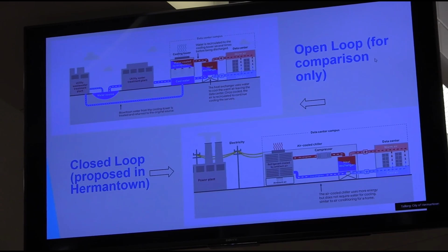These technologies have been around a long time. It's important to note that we're operating non-evaporative cooled data centers today, but even an evaporative cooled data center has a closed loop. Looking at this figure for comparison, on the evaporative cooling side there's an open loop where water is brought in and evaporated, and that evaporation provides the cooling—but there's also a heat exchanger and a closed loop system on the inside.